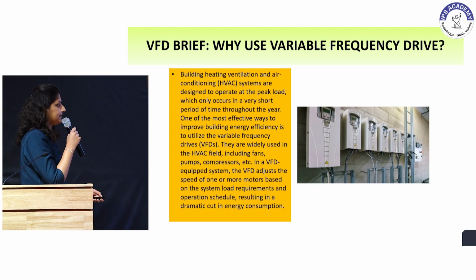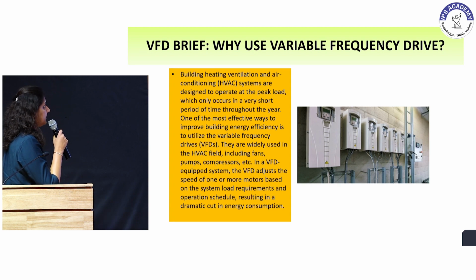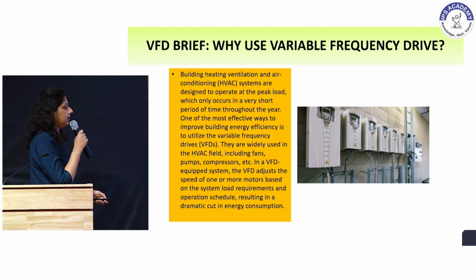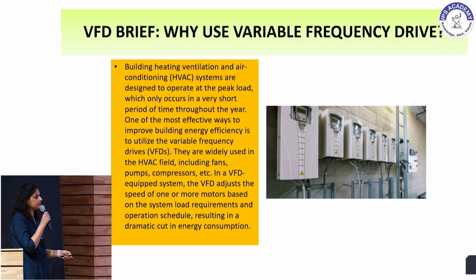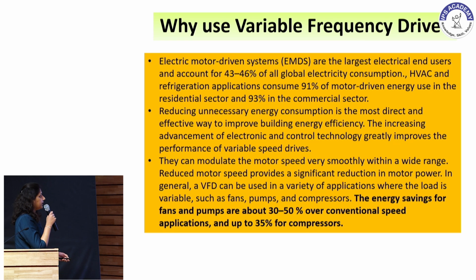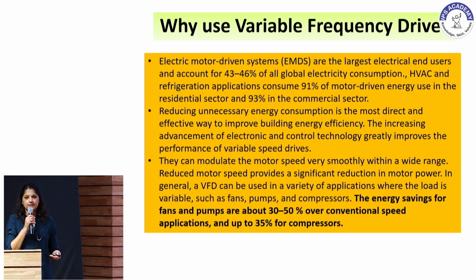We have also experienced in today's world that VFDs have become a feature which most of the installers want to install in the chillers, hence have become the fifth most important component of the refrigeration cycle or the chiller. So why do we use a variable frequency drive? Because it increases the efficiency of the chiller and also reduces the electrical usage of the complete installation.